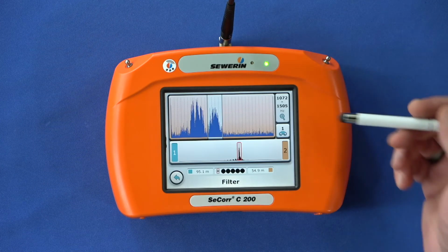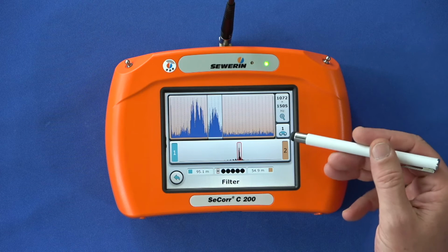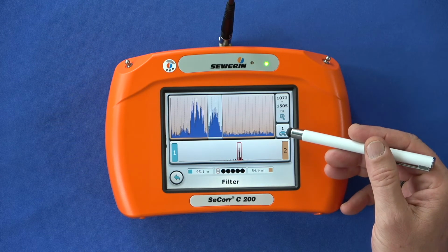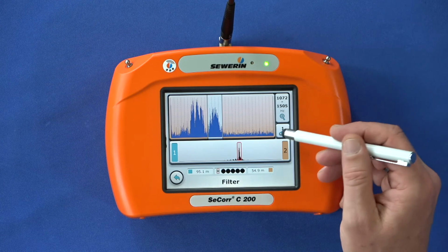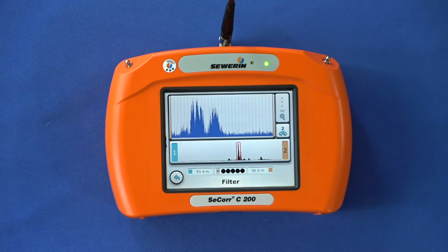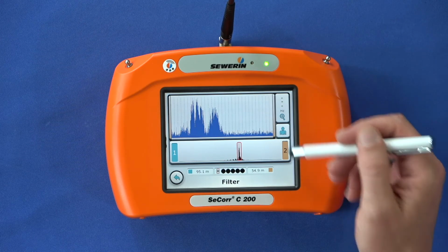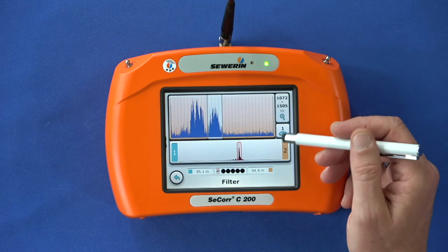In the upper half of the dialog, you can now see the filter base. Various functions are available as a basis for the selection of useful filters, which you can select in the settings. We recommend the coherence function as the factory setting. To the right of the graphic, you can see the currently selected filter limits on a button and below that the information about the current autofilter 1. If you tap this button, you will see the autofilter 2. Tapping again takes you to the manual filter. So you can always switch between the autofilters and the filter you have set manually. Below the filter base, you can see the correlation function.